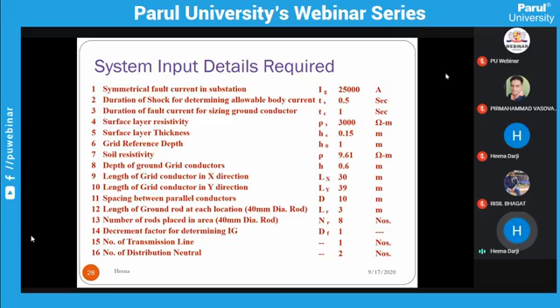In Gujarat, then Rajasthan, and different places, the resistivity is different. Here it is 3000 ohm meter. Now, surface layer thickness: your surface layer thickness is 0.15, which is a standard in IEEE. Now grid reference depth: your grid reference depth is 1 meter.